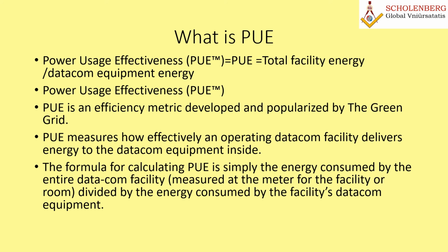The formula for calculating PUE is simply the energy consumed by the entire datacom facility, measured at the meter for the facility or room, divided by the energy consumed by the facility's datacom equipment. So PUE equals total facility energy divided by datacom equipment energy.